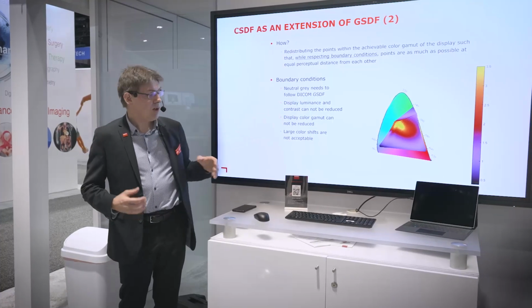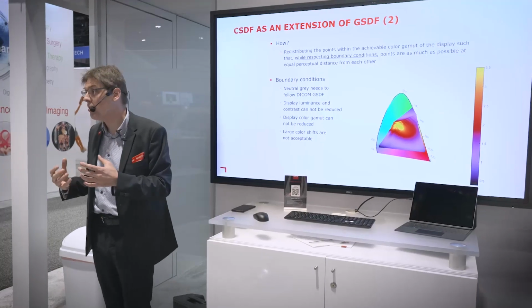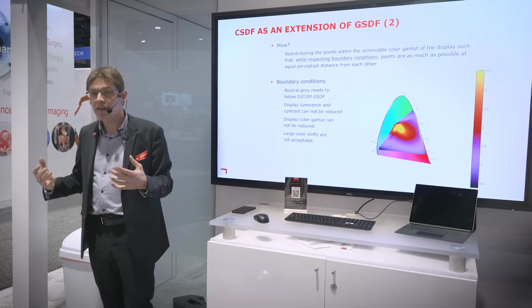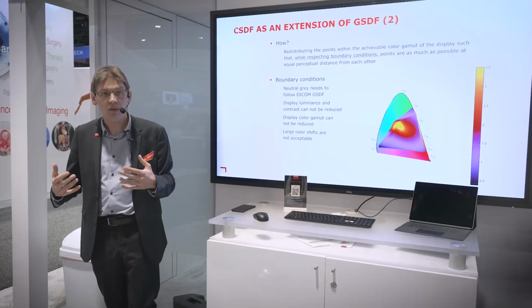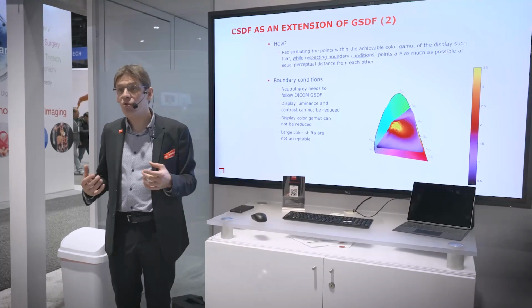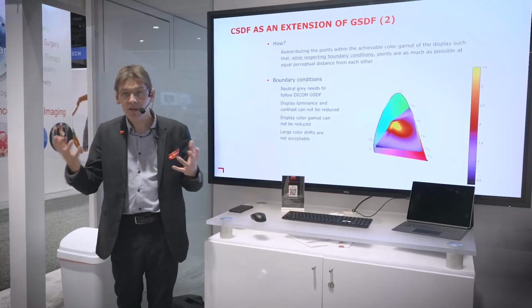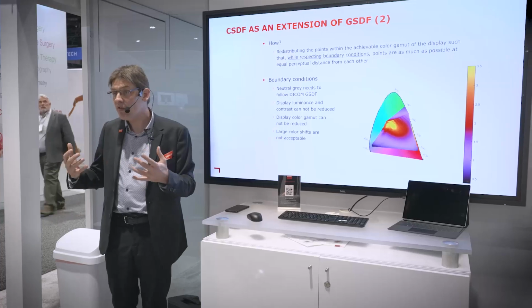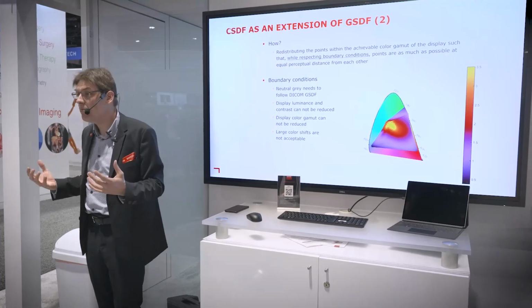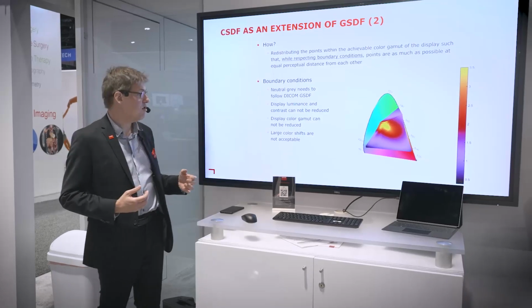Also, you do not want to reduce your display luminance or contrast when changing your color behavior. You don't want to create a dim display because you're optimizing color. You don't want to reduce the contrast. Also, you don't want to reduce your color gamut. So if you have a high quality medical display, like you can see on the booth here, with vivid saturated colors, yeah, you want to keep that. You're not going to make it a less saturated display.